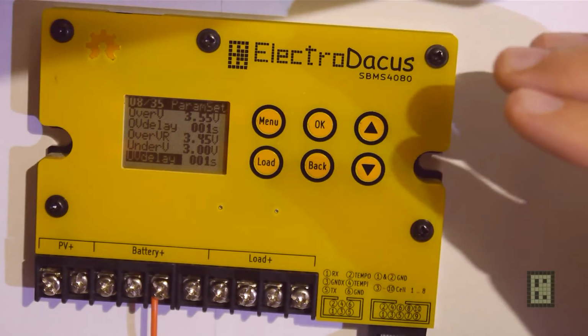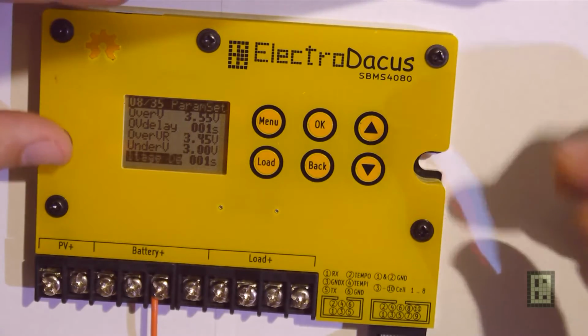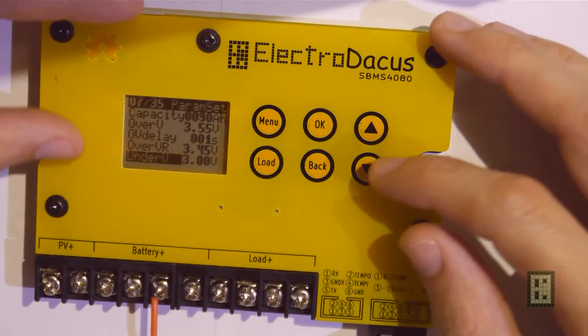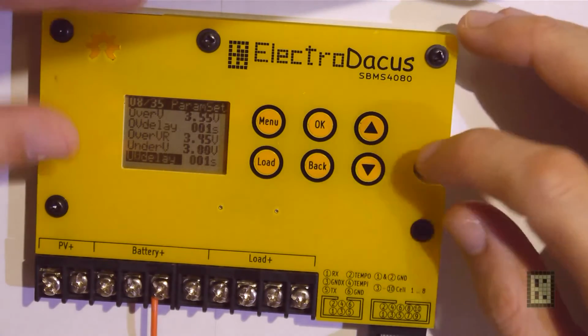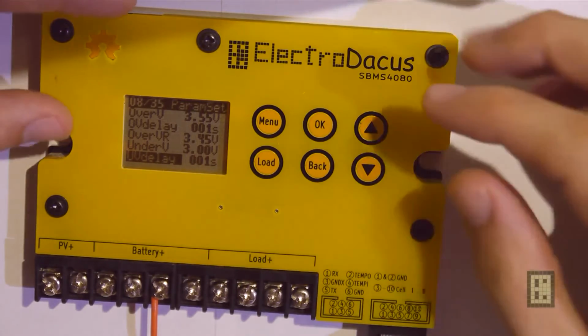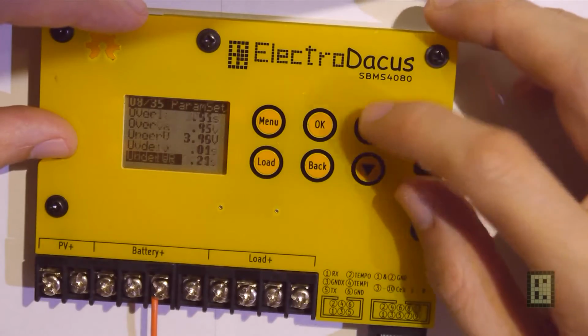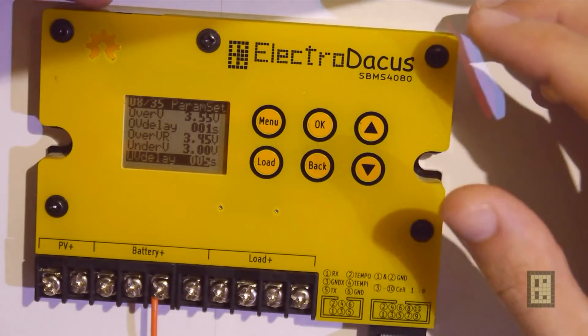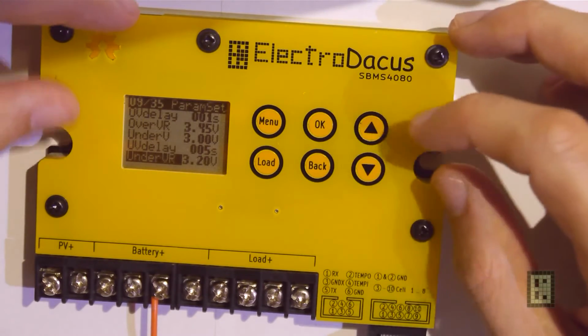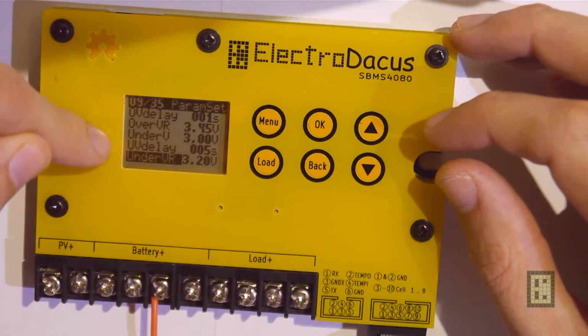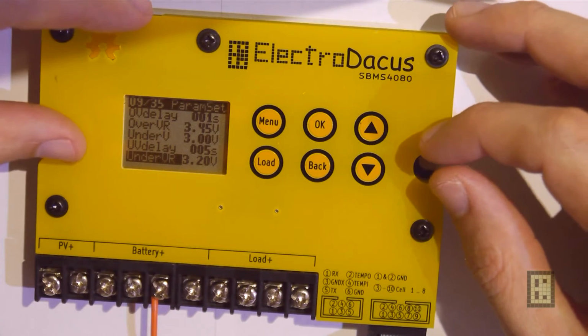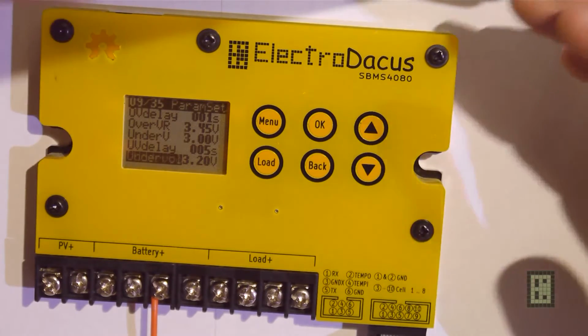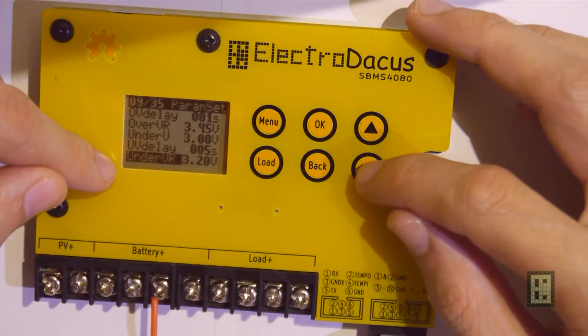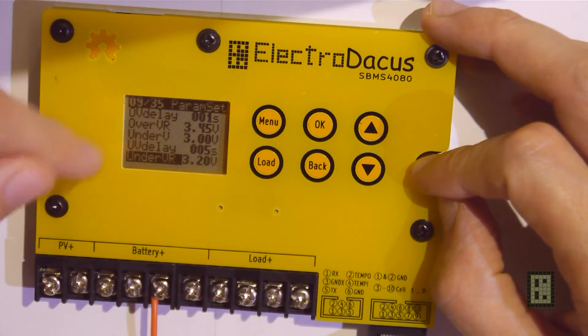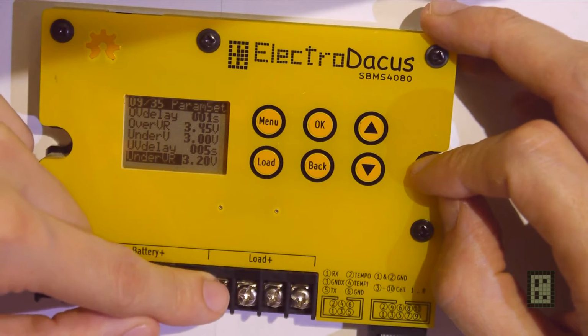Maybe you have a load that is quite harsh on your batteries, and maybe one of the cells will go under 3 volts, but your battery is not discharged, it's just that the load is very heavy for 2 or 3 seconds, and you don't want to disconnect the load. Then you just come here and select how many seconds you want to wait before it cuts off the battery when that under voltage is exceeded, or when any cell is below that set voltage. And then this is under voltage recovery: when the lowest cell goes above this 3.2 in this case, then the load will be reconnected automatically.